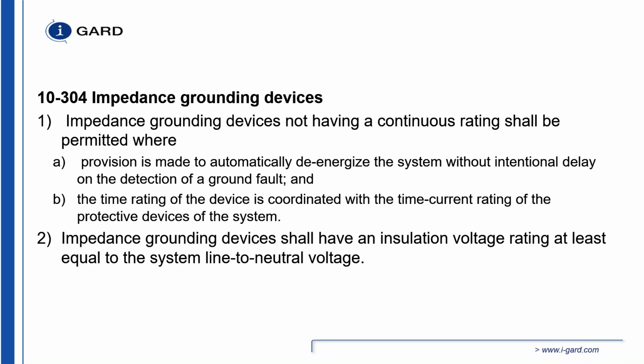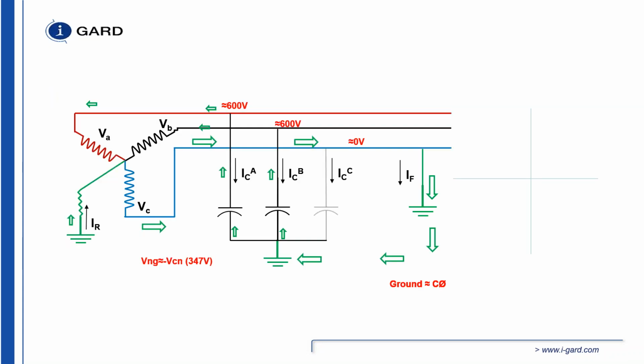So if you have a 4160 volt system and you have a 2400 volt 400 amp resistor on that system, then you can actually have a 6 ohm resistor, and we have to monitor whether that resistor becomes short or becomes open. That may be very difficult to do for some people, but we have found a way to actually make that work and detect that circuit. So we're going to discuss here why I believe a resistance grounded system having a distributed neutral is particularly unsafe.